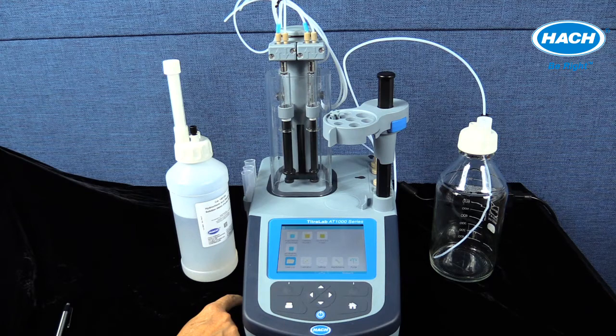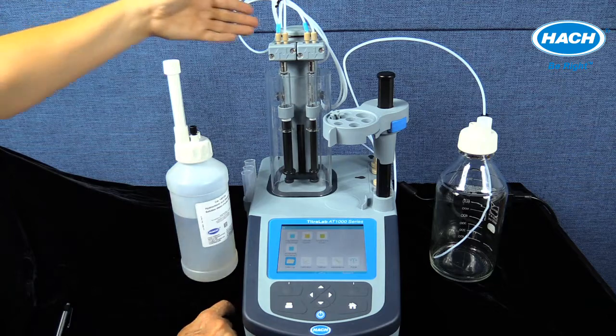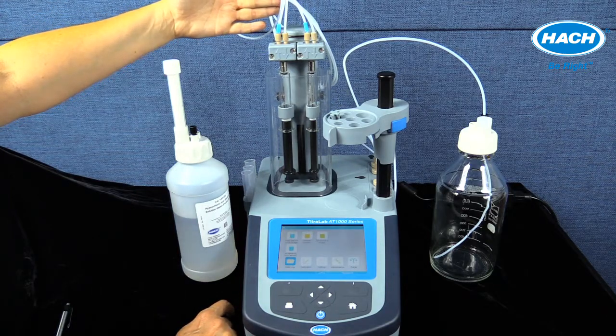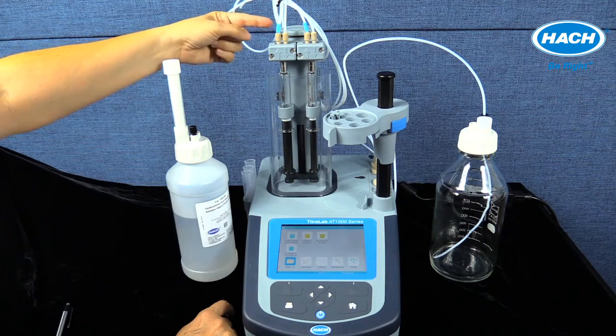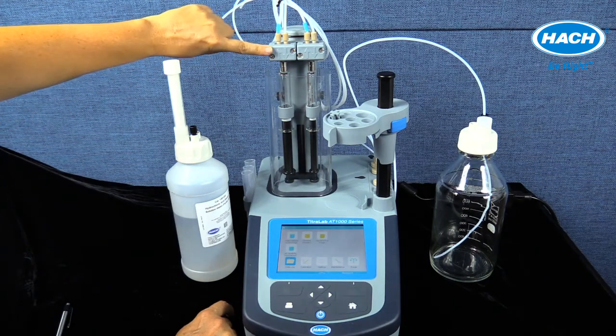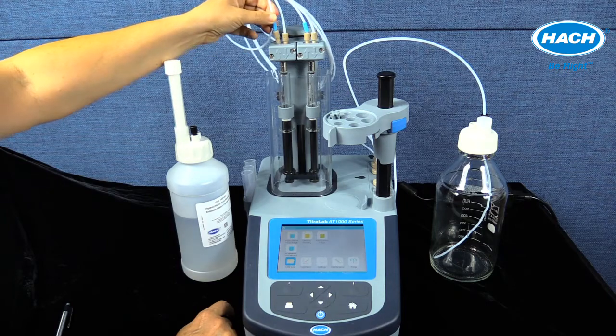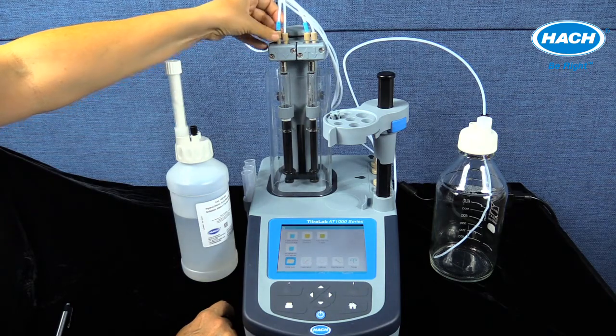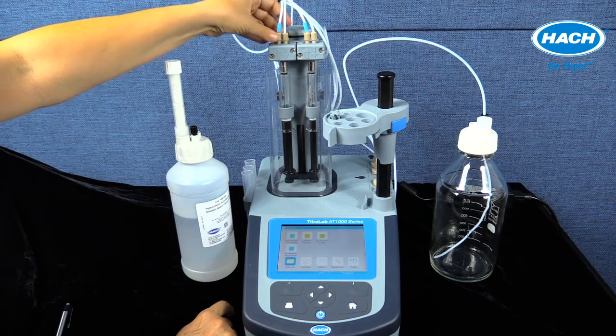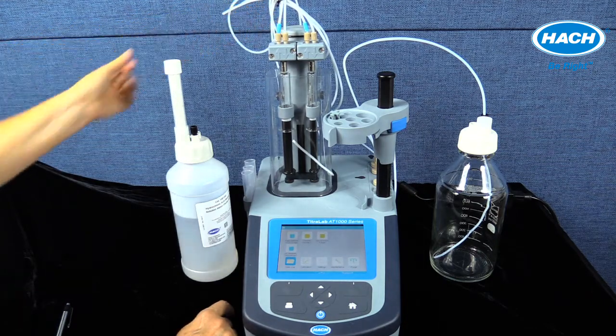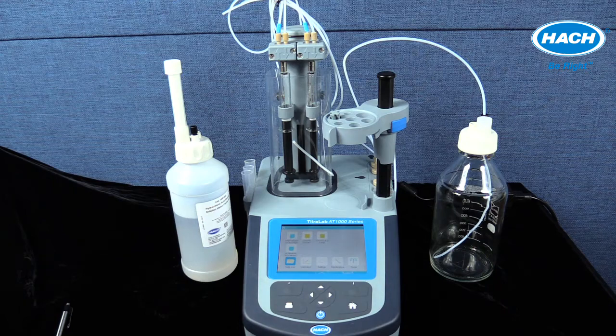Purging the syringe to remove old titrant and air bubbles is performed through the software. The software is also able to track or schedule maintenance or replacement of the syringe and syringe components. The tubing for the syringes is pre-installed on the instrument. The direction of the titrant flow is easily recognized by the up and down arrows. The blue indicators on the syringe tubing are installed to indicate delivery tips and installed in the port with the upward arrow. Tubing is easily installed by simply screwing in the tubing connectors into the correct port until a click is heard. The procedure for each application will detail the appropriate tubing to conduct that titration procedure.